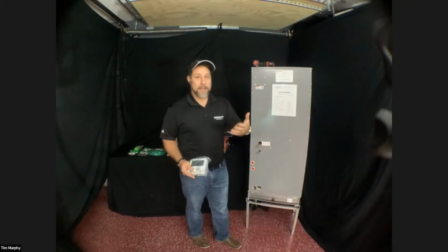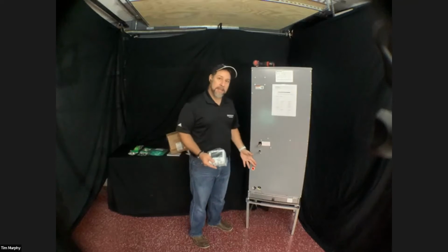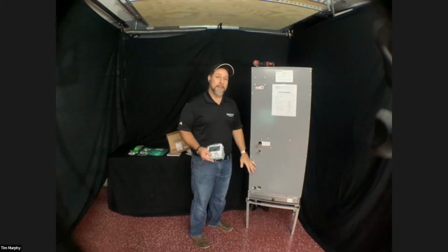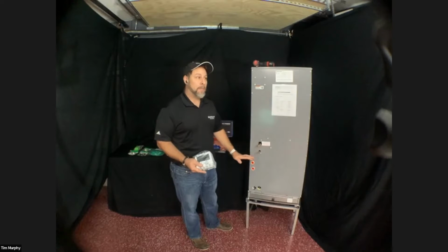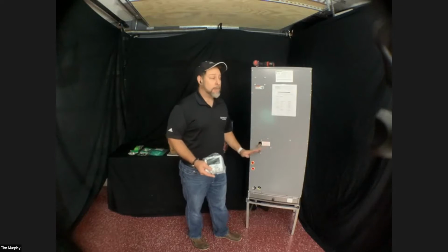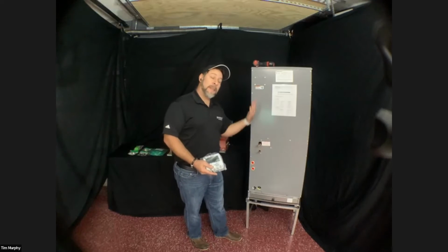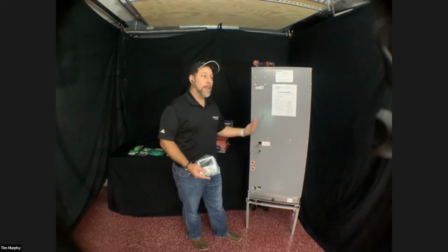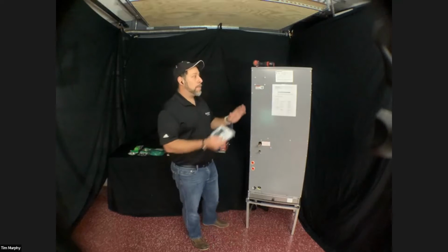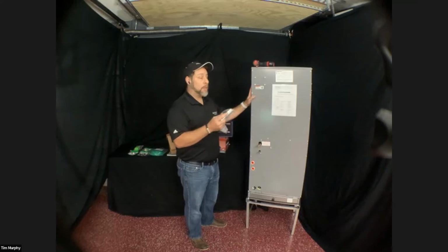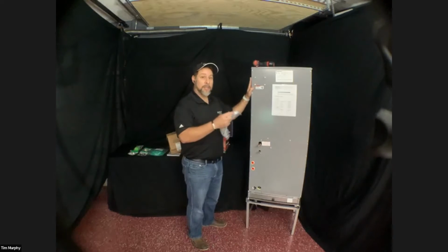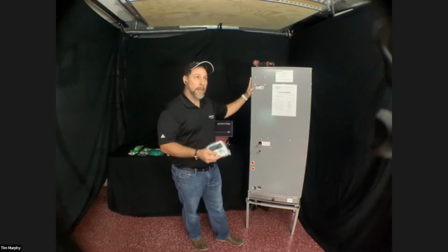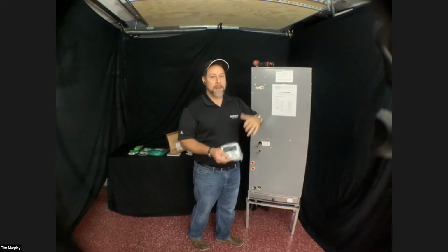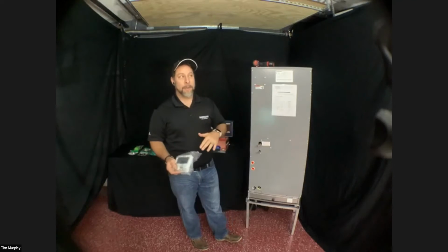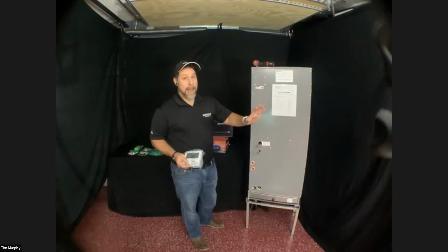But as you guys know, once the coil rises in temperature, once it stops dehumidifying the home and providing cooling, there have been times where that moisture, if the fan is continuously running, will blow back into the home. So just like with the high walls, you can set the fan so it shuts off on thermal off. Thermal off meaning if it reaches heat, the fan shuts off. If it reaches cool, the fan shuts off. That also applies to our high wall system.